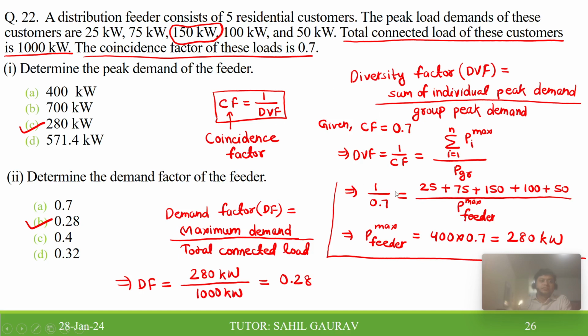So from the coincidence factor you can find the group peak demand. Group peak demand means the feeder, because all the power comes from the feeder, and it has several customers. The individual peak demand is given for different durations of time, because at certain times many customers are taking power. So how can you find the peak demand for the feeder? Based on this, for calculation, practically this is the maximum, the P max of the feeder.